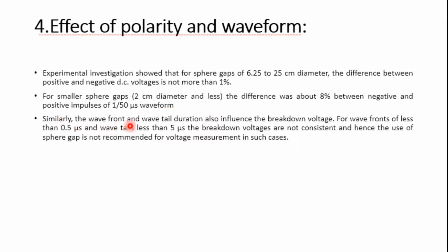Similarly, the wavefront and wave tail durations also influence the breakdown voltages. For a wavefront time duration of less than 0.5 microsecond and a tail time of less than 5 microseconds, the breakdown voltages are not consistent. Hence the use of standard spheres is not recommended for voltage measurement in such cases, because of the very short rise and fall times.